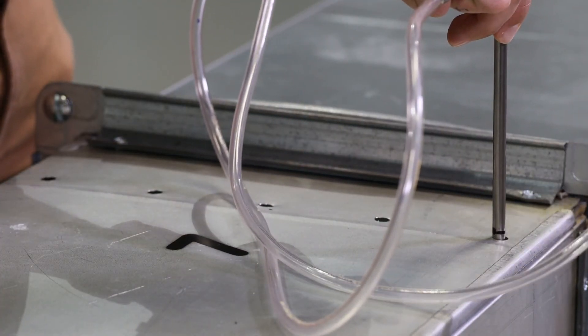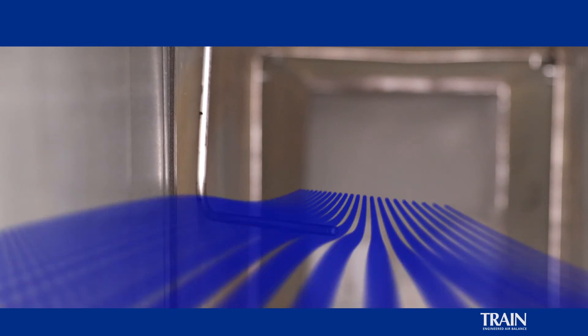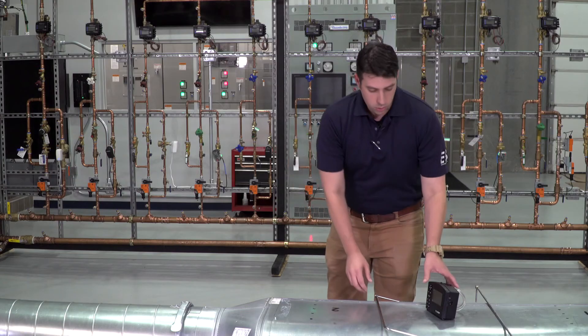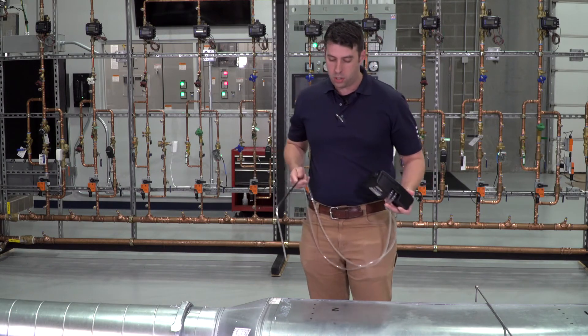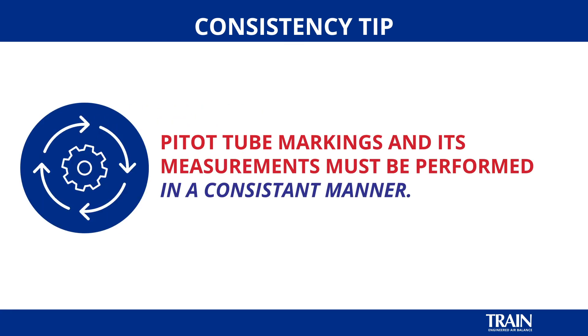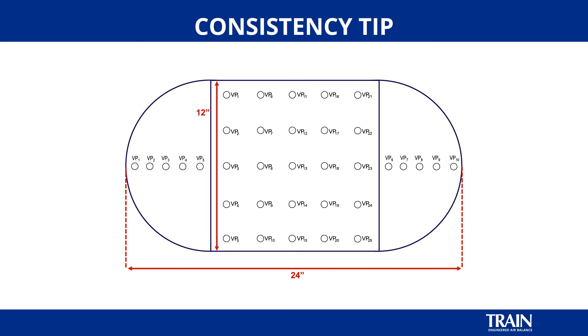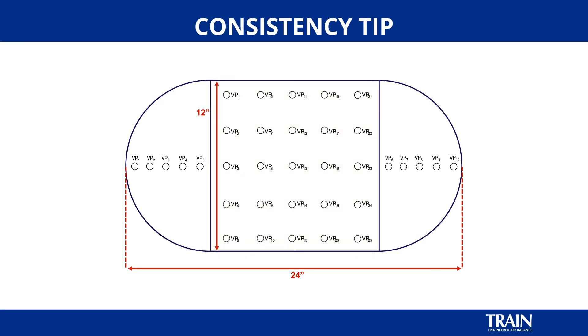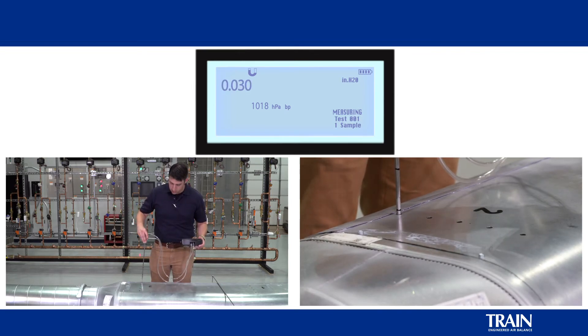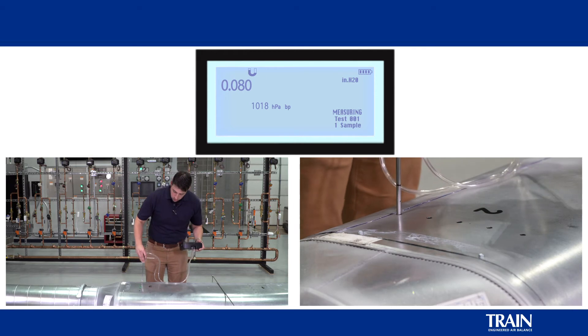Here we can visually demonstrate the location of the pitot tube inside of a duct when performing a pitot tube traverse. The pitot tube must be oriented into the airstream and perpendicular to the airstream in a cross-sectional plane. We do not want to see the pitot tube at an incorrect angle, since that will produce erroneous readings and provide unacceptable data. We will take the pitot tube and begin traversing the rectangular portion of the flat oval duct. It's also important that the pitot tube be gridded off and measurements taken in a consistent manner. For the purposes of this demonstration, we will proceed with a top-down, left-to-right grid pattern, which is recommended for consistency to produce repeatable results. Point number one, point number two, point number three, point number four, and point number five.